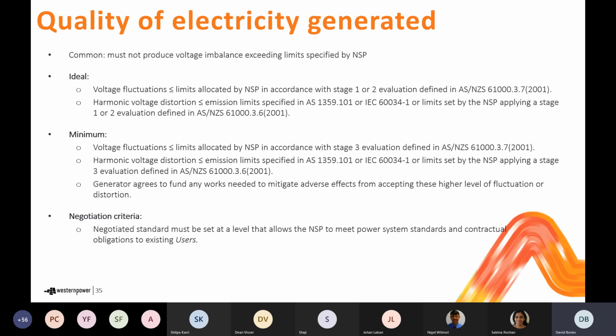And that's been achieved by tying the requirement to the allocated distortion levels that the network service provider has specified the generating system meet, through the process described in chapter 2 of the technical rules. The ideal and minimum are somewhat similar, the difference being that the minimum allows for those acceptable distortion levels to be set through a stage 3 evaluation process, which tends to give rise to more relaxed levels.